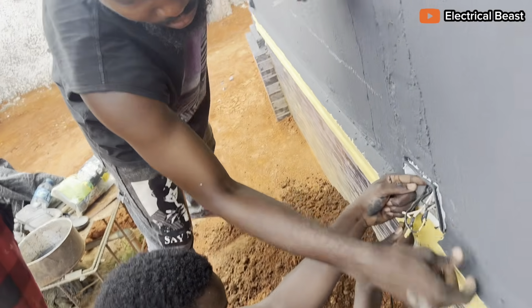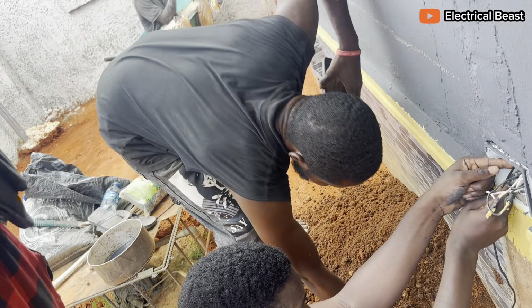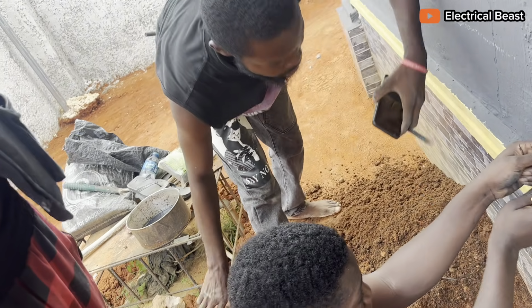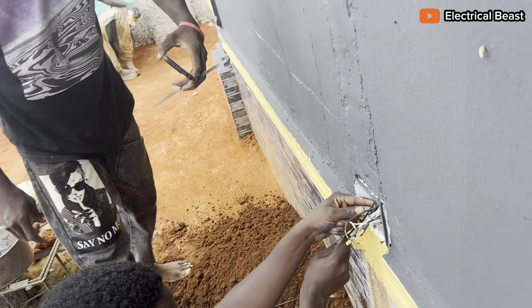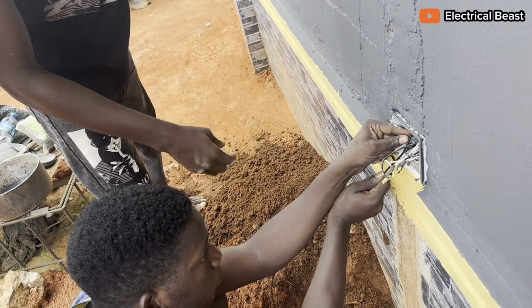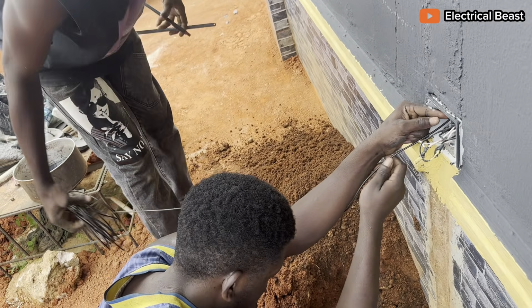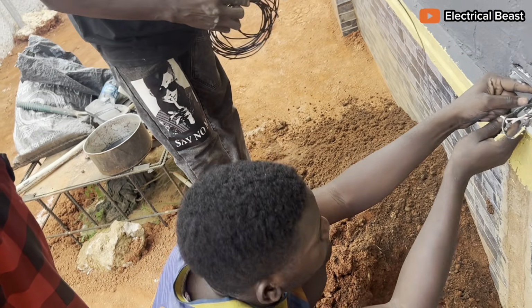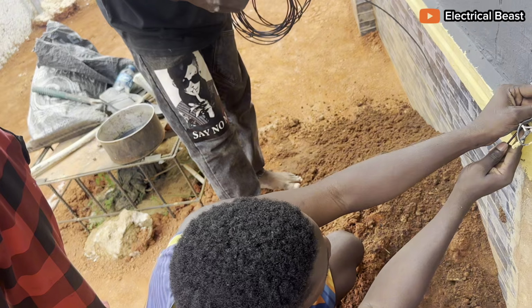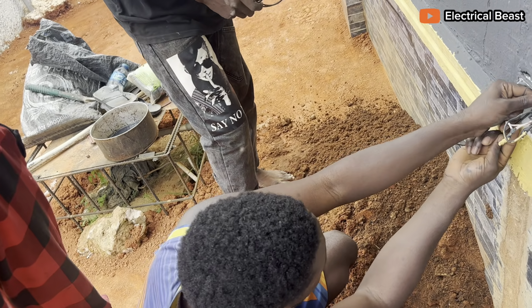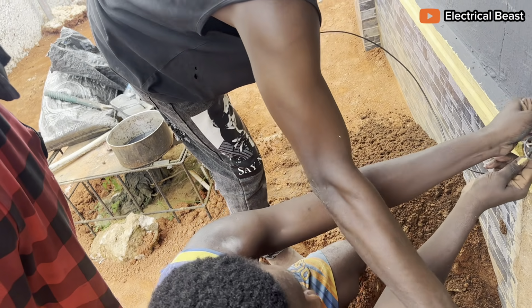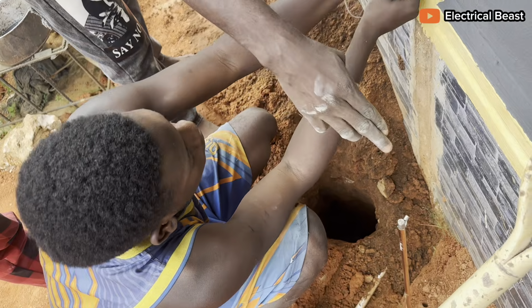So let's check other stuff. So this is the earthing. So we have the earth rod here. Then this is the earth wire. We are going to take this earth wire directly to the surge protecting device. There's an earth terminal there, so we add the surge protector to protect the inverter from lightning strikes. So we have an earth rod here. We're just going to connect the wire to the earth rod. That's all.